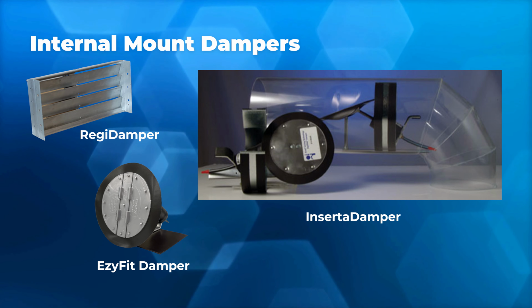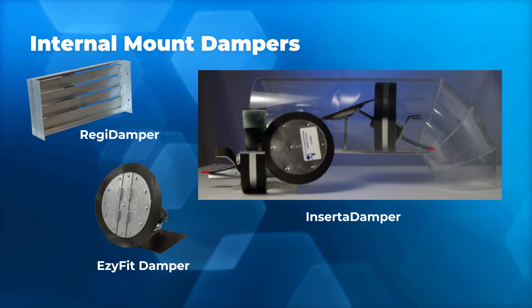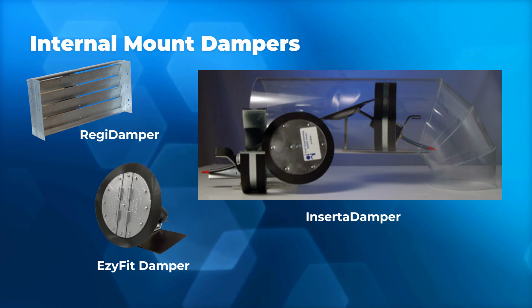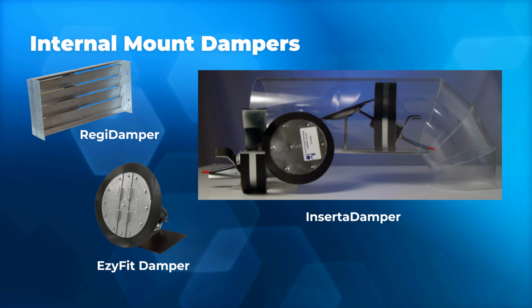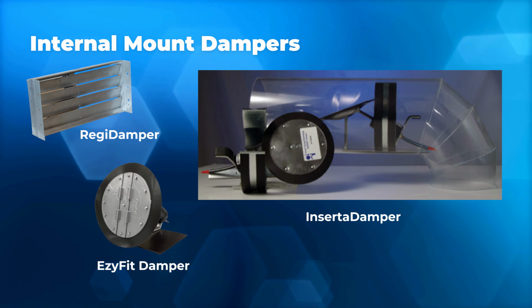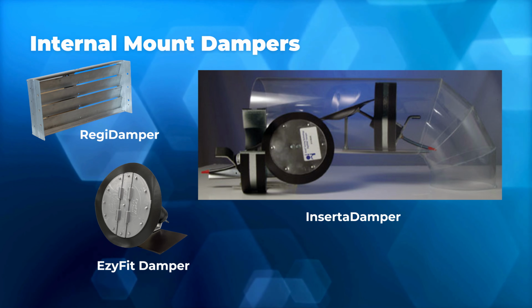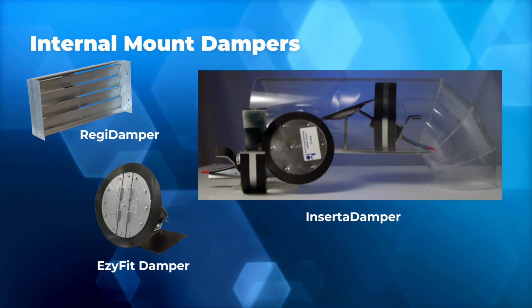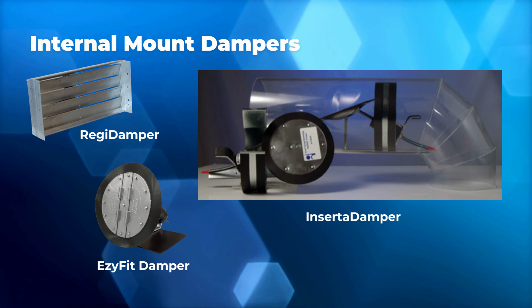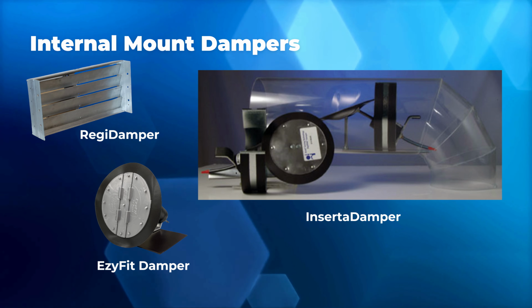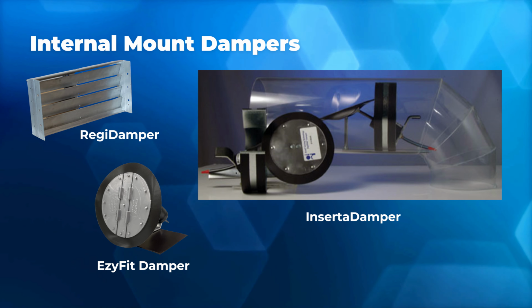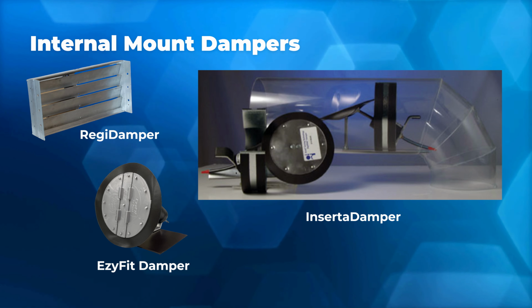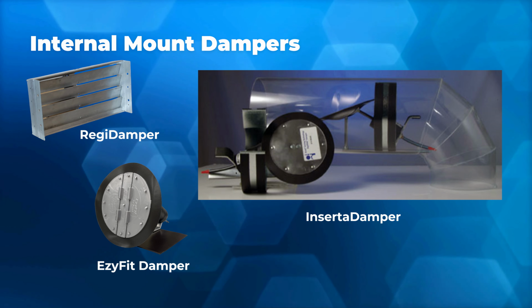And typically you'll use these if they have a finished basement or plans to finish off the basement. That way you're able to get to the damper in the future if there's any failures or anything like that in the system. The first option there on the left is our Regi damper. This is going to sit right underneath the register grill itself. You basically put it in with 2 screws to hold it in place, and then you silicone it in place. That's what holds it there.